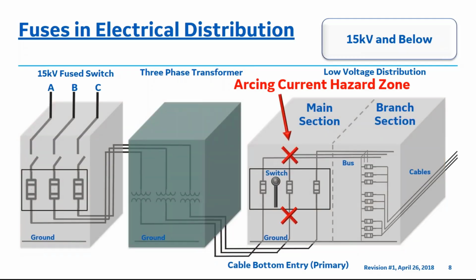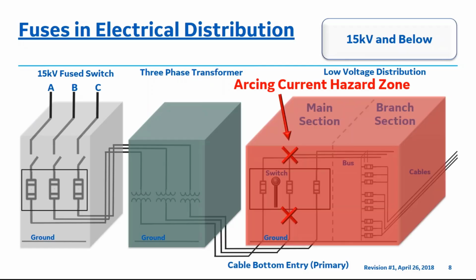The third example of arcing faults is between the primary as well as the secondary side of the low voltage fuse switch or branch section. If bus bar or cable connections between the primary or secondary side of the low voltage fuse switch located in the main section and the fused low voltage branch section are utilized, during these arcing fault events inside the distribution section, an arc can propagate and ricochet inside these sections and affect the immediate arcing current hazard zone within this three-dimensional area on the low voltage side.